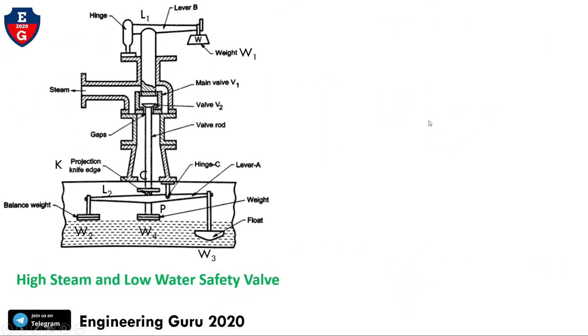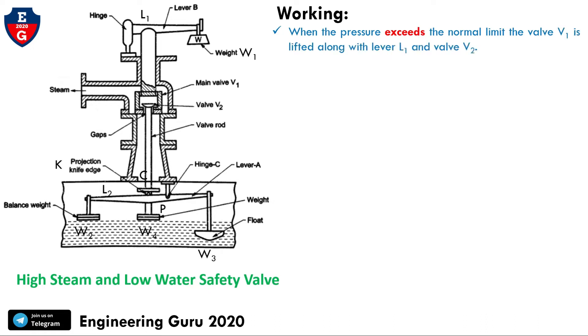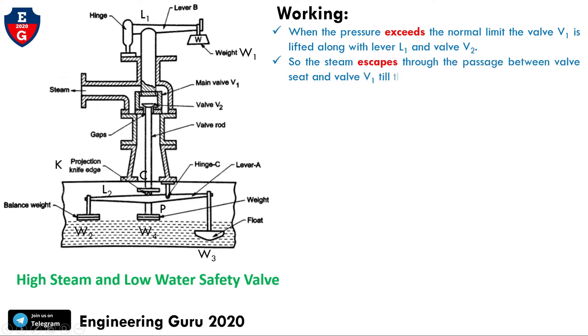Now we will see the working of this safety valve. When the pressure exceeds the normal valve limit, valve V1 is lifted along with lever L1 and valve V2. When the pressure exceeds the design limit, steam escapes through the passage between the valve seat and valve V1, until the pressure returns to normal.